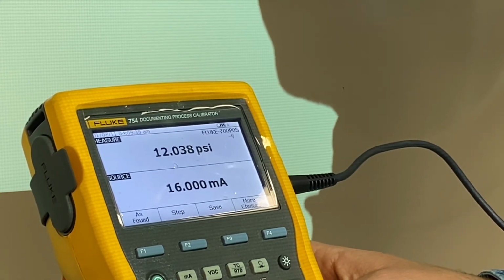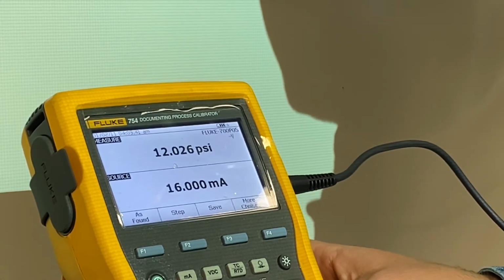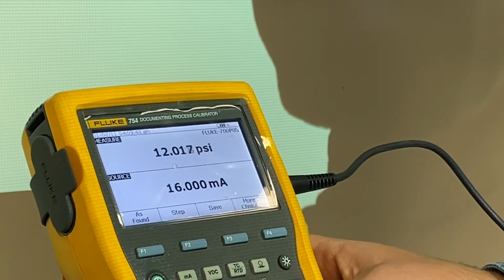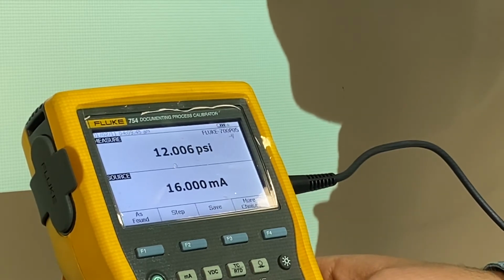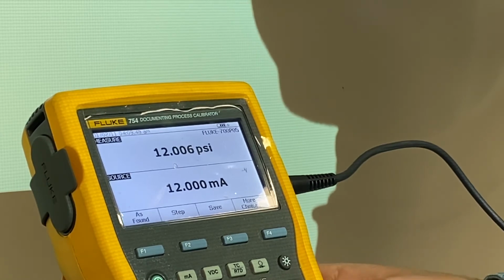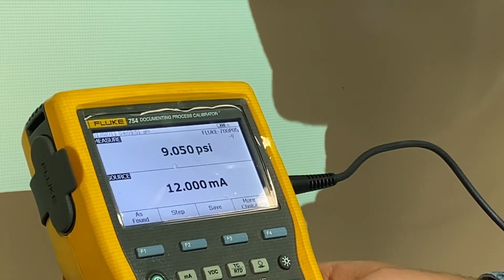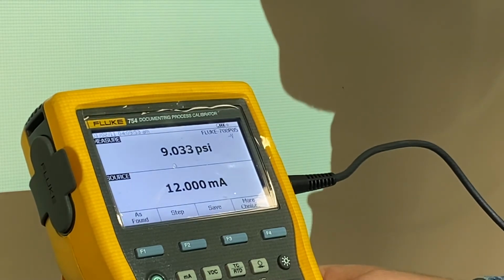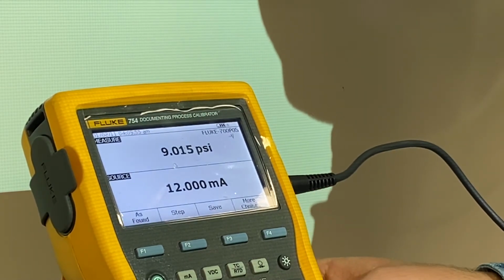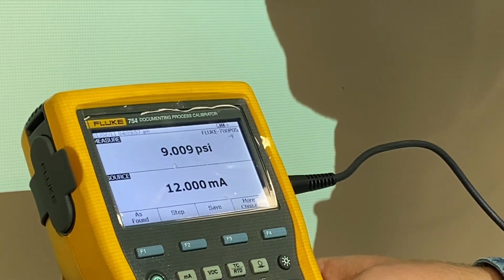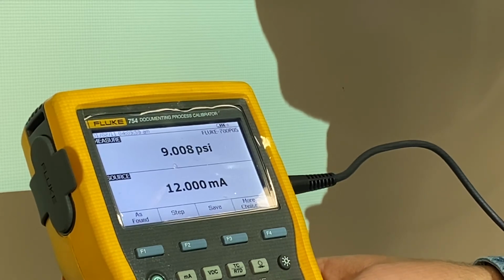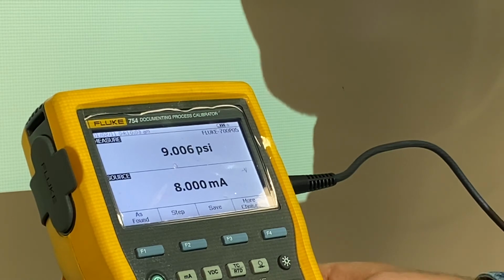At 16 milliamps, we should be at 12 psi. Okay? At 12 milliamps, we should be at 9 psi. Okay, that looks good. At 8 milliamps, we should be at 6 psi.